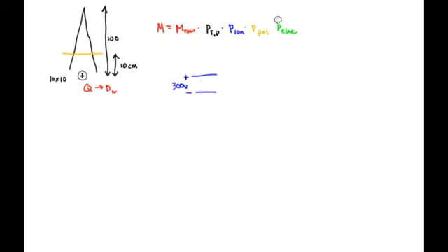And then the final factor is P electrometer, and that's relatively straightforward. It just says if you measure a certain charge in your chamber, is that really the charge, or is the electrometer not quite efficient? The correction is typically less than 1%, and the way you get it is you don't do that measurement in the clinic. You instead send the electrometer away to the calibration lab, typically with your chamber, and they tell you what the collection efficiency is. So those are the factors.